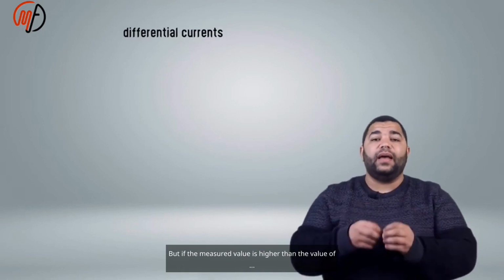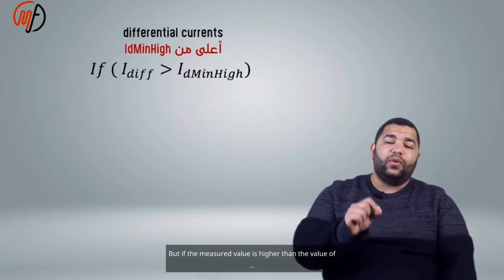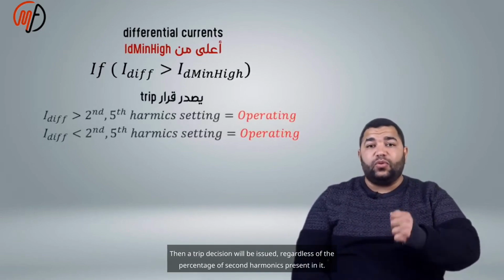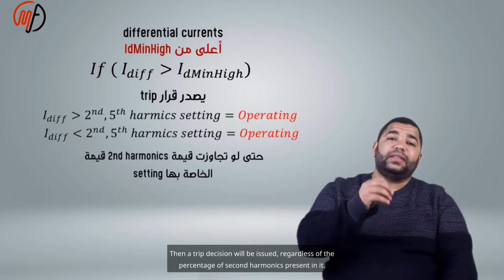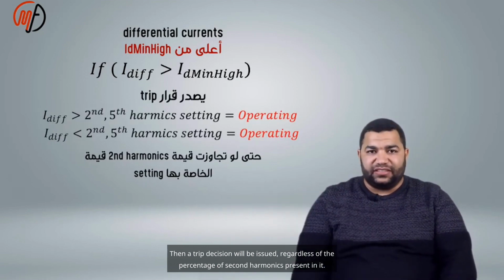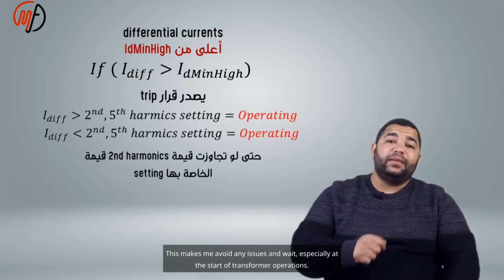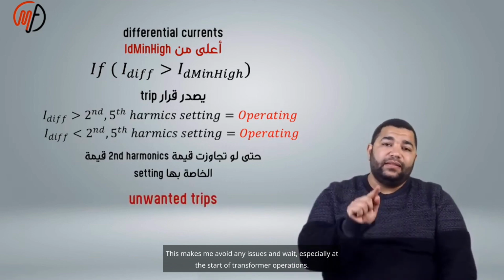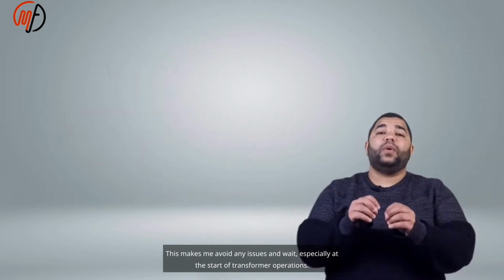But if the measured value is higher than the value of IdMinHigh, then a trip decision will be issued regardless of the percentage of second harmonics present in it. This makes me avoid any issues and wait, especially at the start of transformer operations.